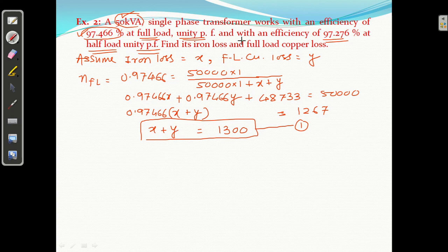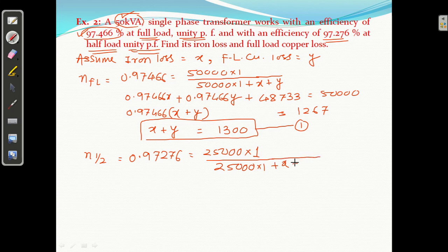So second: efficiency at half load is given as 0.97276. This equals 25,000 (half of full load KVA) into power factor 1, upon 25,000 into 1 plus x. Iron loss will not change, but y will become y by 4, since copper loss at half load becomes 1/4, so it is 0.25y. Iron loss remains same at any load, but copper loss becomes half squared at half load.